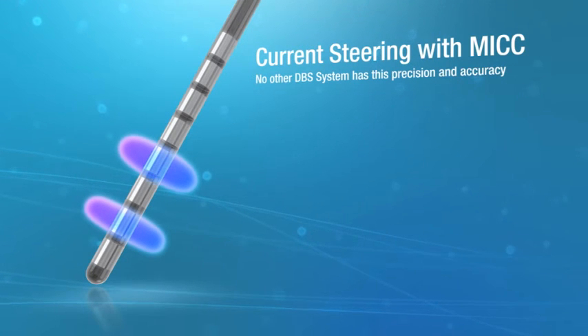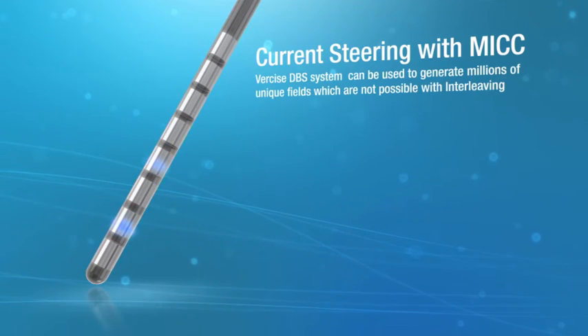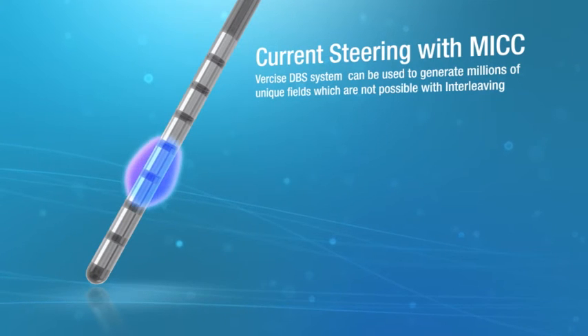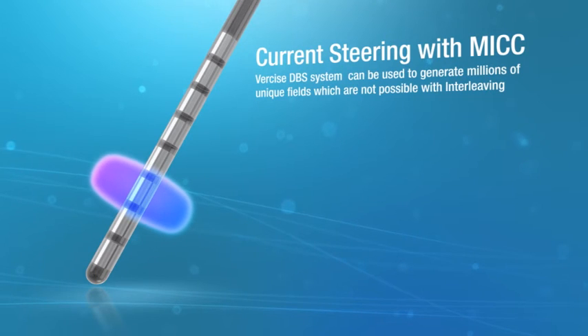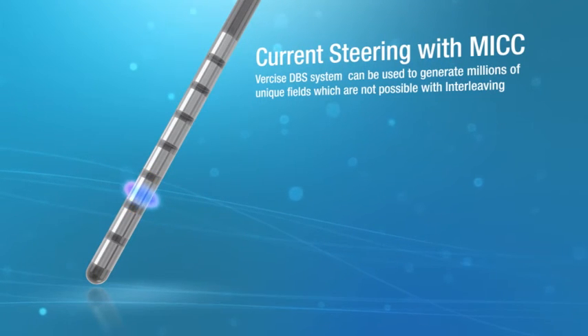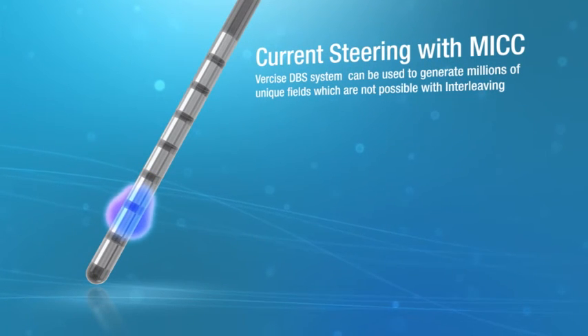Therefore, each contact powered by the Vercise DBS system can be used to generate millions of unique fields, each area or setting having different amplitudes, pulse widths, rates, and contact configurations, which are not possible with interleaving.